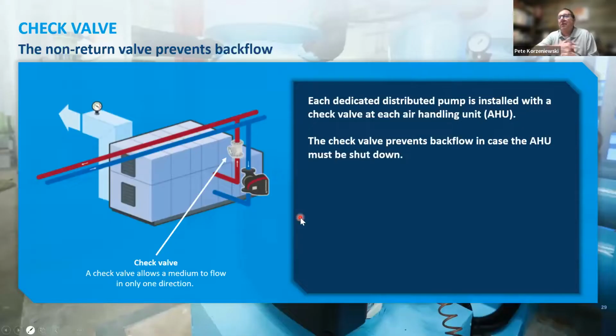The last piece of hardware is just a simple check valve. Ideally, we want a check valve that's got a low pressure drop, and we're going to put that on the hot side or the return side of the air handler, just to ensure that we don't get any backflow in any air handlers that aren't calling or don't have load at that particular moment in time.